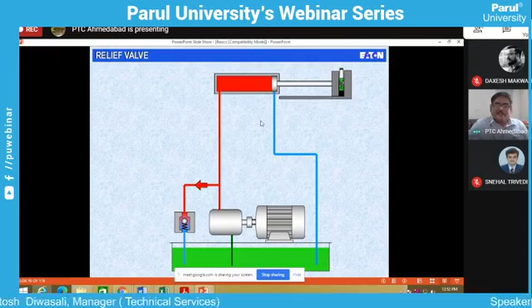When I operate my pump using the electrical motor, the system will start moving and my work will get done. But when this piston stops moving at the end of the stroke, the fluid will get resistance and no further fluid flow is possible in the cylinder. So the fluid will now start moving towards the relief valve. And this relief valve spring is rated in such a way that after this particular work is done, the ball valve will unseat and the fluid will be transferred back to the tank, and can safely handle the entire hydraulic system. So this is how a pressure relief valve functions in a hydraulic system.